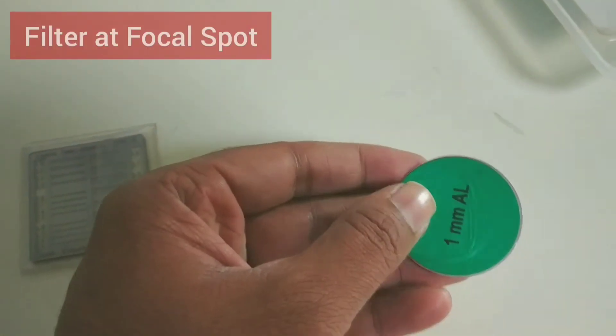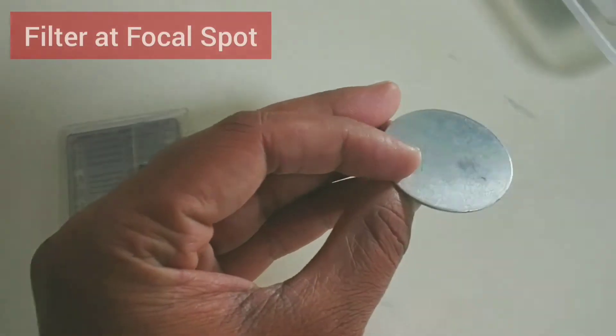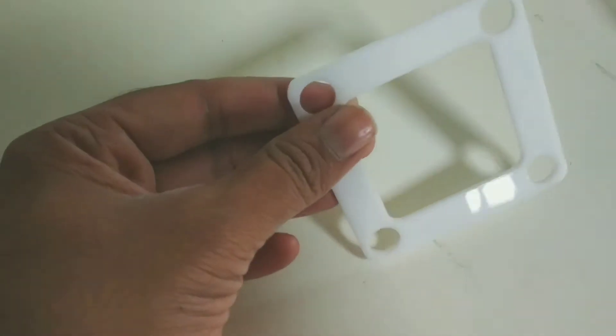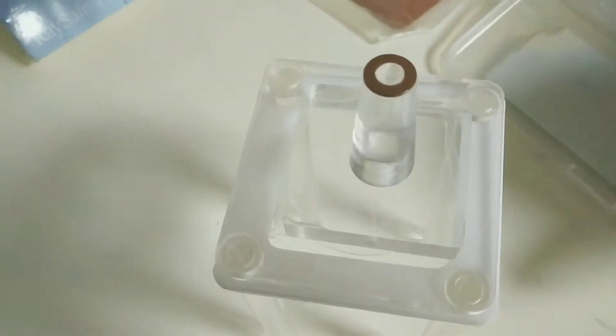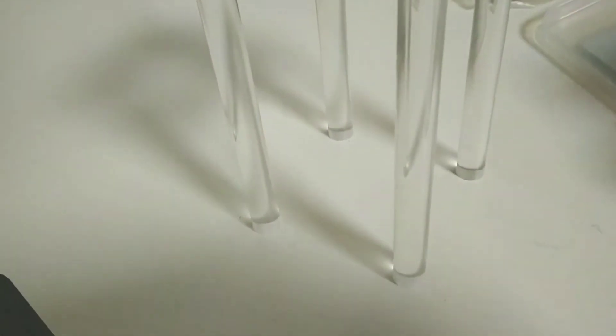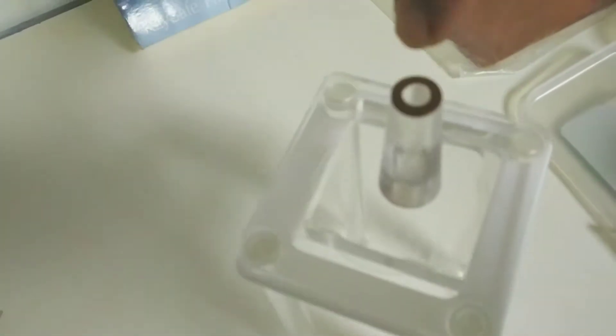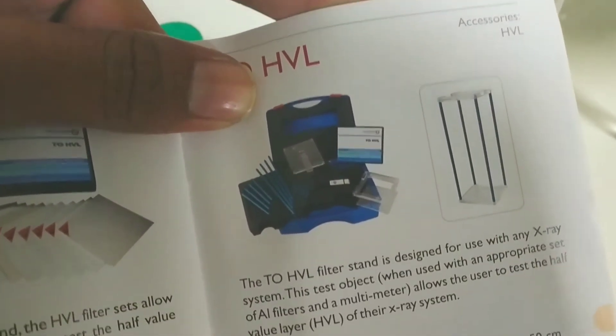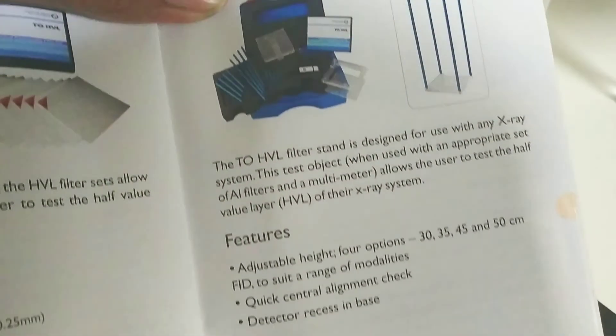This filter is used at the focal spot of the X-ray. It is kept at the front of the X-ray tube. You can see one copper circle is present on the upside. The TO HVL filter stand is designed for use with any X-ray system.